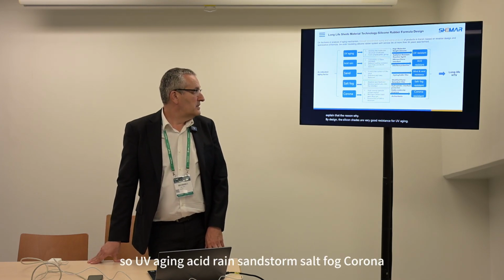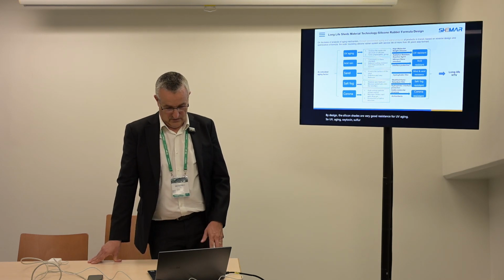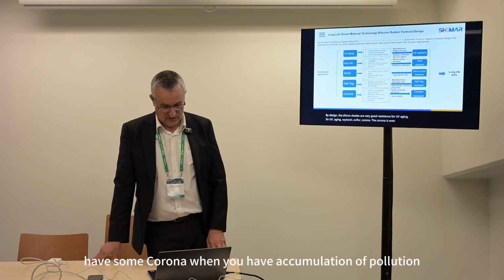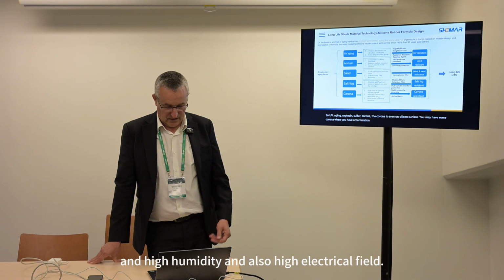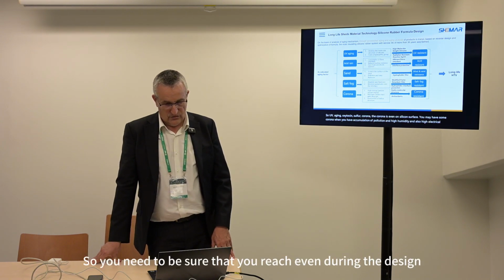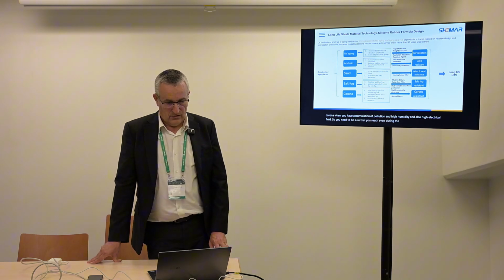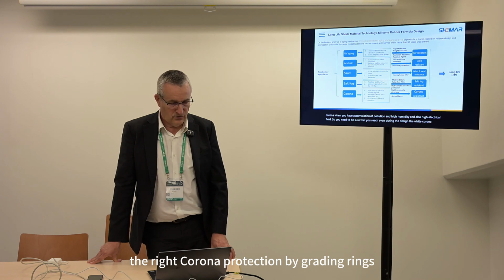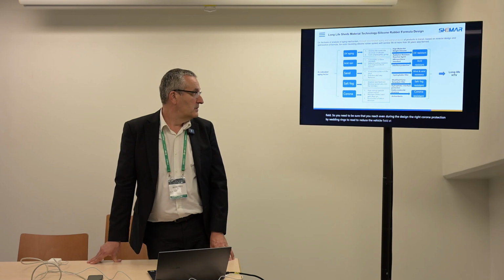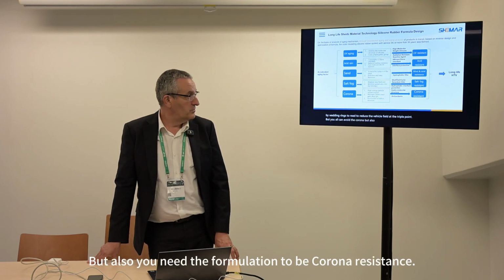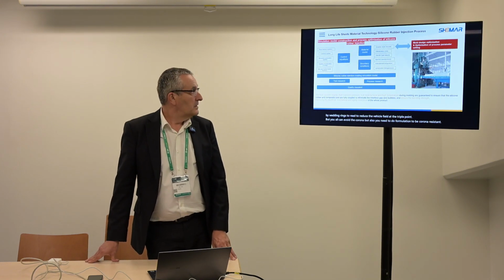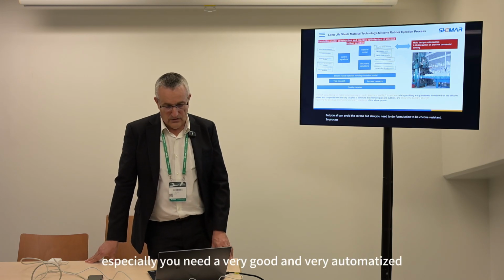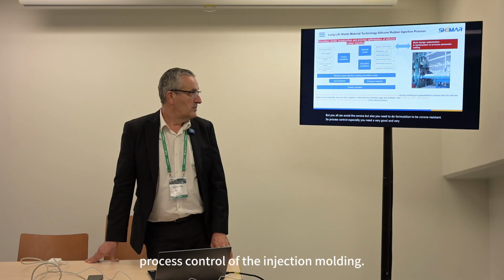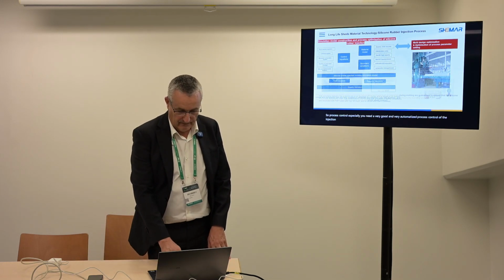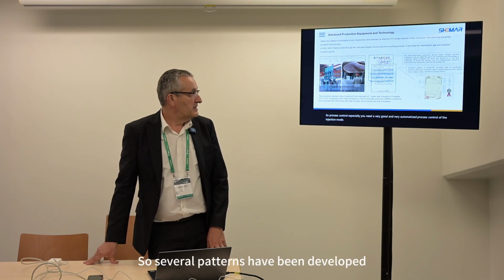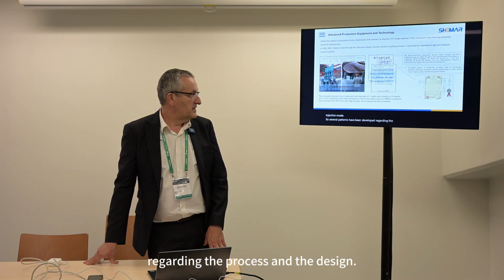So UV aging, acid rain, sandstorm, salt fog, corona. Even on a silicone surface you may have some corona when you have accumulation of pollution, high humidity and also a high electrical field. So you need to be sure that, even during the design, you reach the right corona protection by the grading rings to reduce the electrical field at the triple point, so that you can avoid the corona, but you also need the formulation to be corona resistant. Process control is also key: you need a very good and very automatized process control of the injection molding. Several patents have been developed regarding the process and the design.